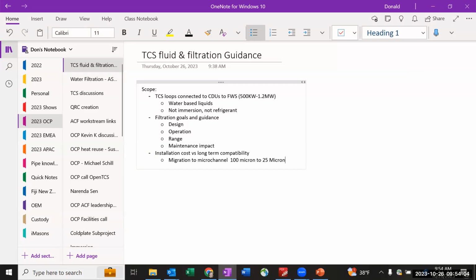Hold on, Don. I think I might be missing something you're bringing up here, because you're saying you need to pull out the whole loop, and I'm with Mike, where if they were going to add a microchannel server down to 50 or 25 microns, I don't know that you'd have to pull out the entire loop, but you would have to go back to where your filtering processes are and see if, like we said earlier, either it needs to change at the CDU, or...